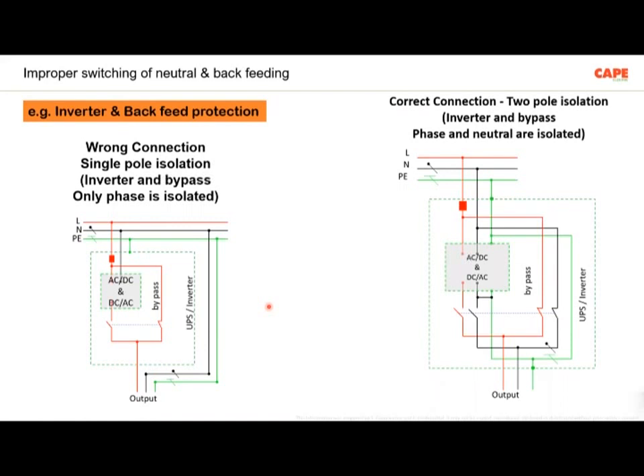One example is the inverter. Most of the inverters which we use in our residences and houses have only single phase changeover. Only the phase is changed over. The neutral is not running through the inverter. The same neutral is circulating everywhere. This can create a backfeeding and shock hazard. A lot of incidents are recorded. Plus, this can also create insulation failures, and this can also create fire hazards.